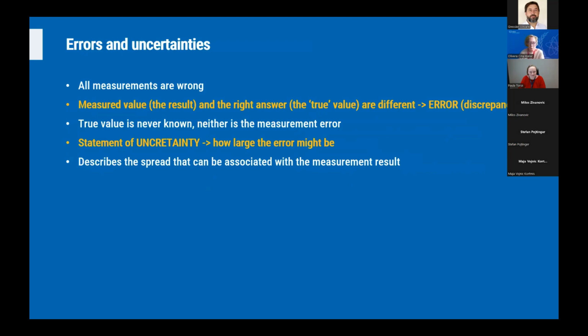But we know when we discuss the uncertainties and accuracy that all measurements are wrong to a certain extent, and what we perceive as an error is in fact a discrepancy between the measured value and something that is considered a true value. Of course, the true value is not known, and by virtue of that, the error is not known, which is why we use uncertainty and try to assess uncertainty in order to have a rough estimate of how large the error might be.